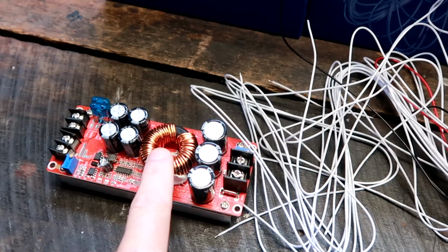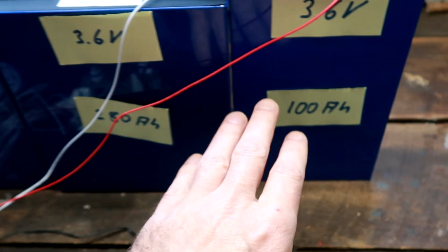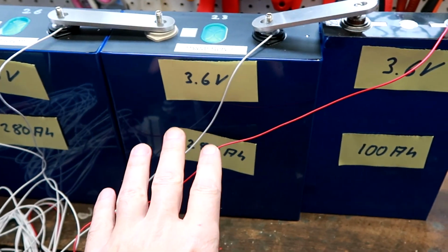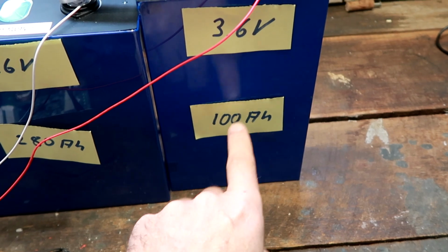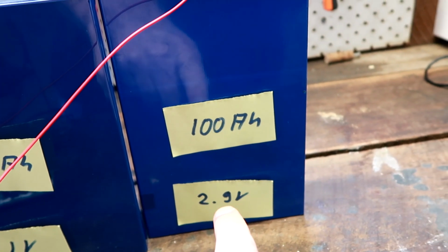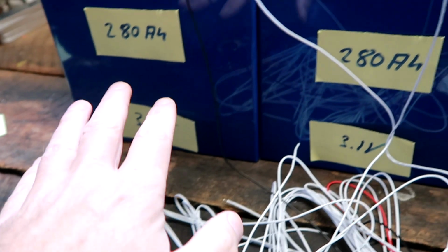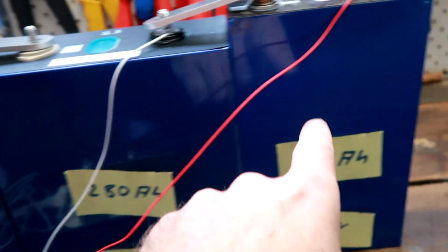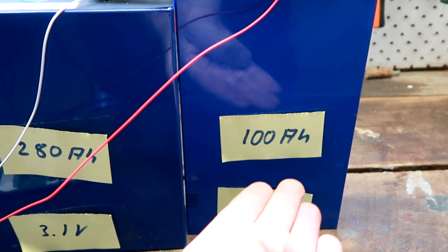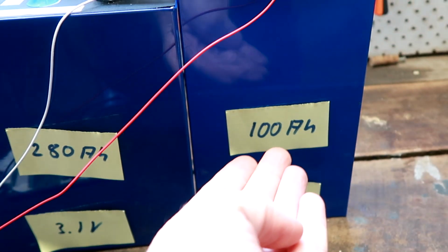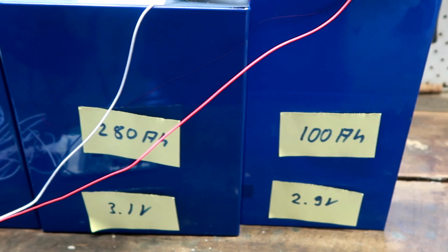And a second thing, or a third thing actually, say if we are taking around 90 ampere hours out of this battery here, all these first three cells here are still fine, but this one is almost completely discharged. So what would happen here? So we've got all the batteries on 3.1 volts now, fairly discharged, while your weakest one is already down to 2.9 volts. With an active balancer now, what would happen? It would transfer energy from these batteries here into this battery, right? To rise the voltage again to 3.1 volts again. It discharges these ones further and lifts this one up. Which is good. This is a good thing.